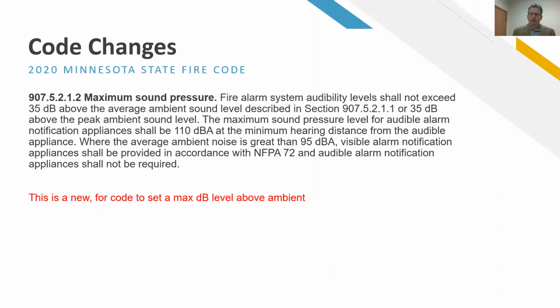So be aware of situations where, instead of adding more audible devices to make a building louder, if areas are already too loud—over 35 dB above ambient—it could become an issue where we'd want to remove some audible devices. I don't think you'd see that often, but there could be areas, like right now I'm in a small conference room—if you put a few horns in this room, we might meet that 35 dB level. Not that you would, but be aware there are applications where that could come into play.